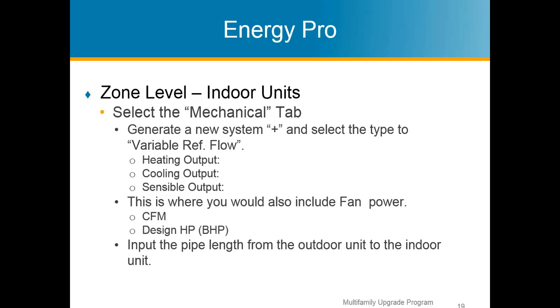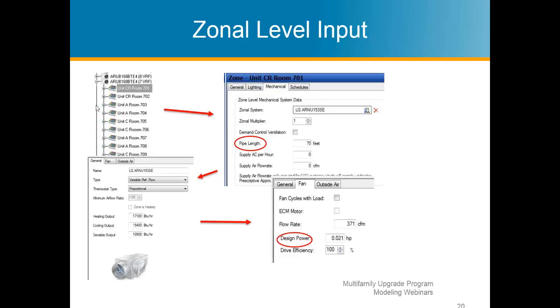You're going to need to calculate your brake horsepower, and I have a slide again to refresh everybody's memory on that. But this is where you're doing all your CFM; your fan energy is all going into the mechanical tab. Similarly, you're going to be putting in your pipe length that's associated to that one indoor unit serving that one residential apartment. That's also going to be put into this zonal level.